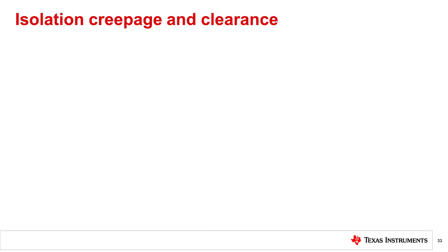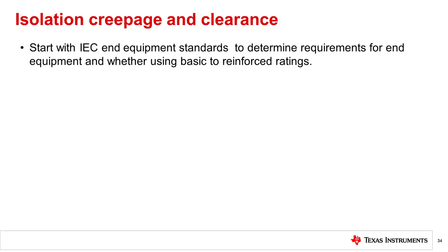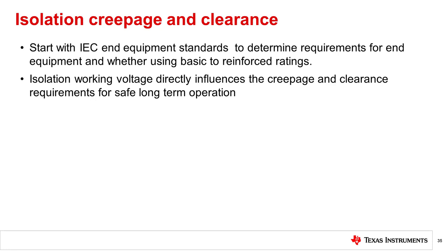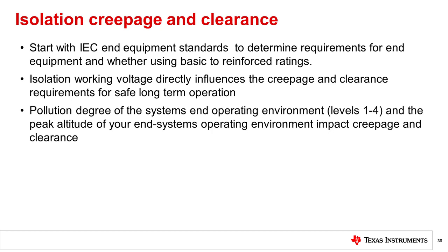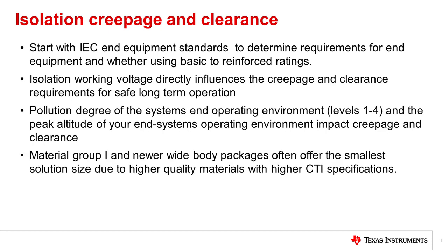This concludes our introduction to isolation creepage and clearance. We outlined a general set of guidelines: understand the required insulation rating of basic or reinforced for your end equipment — the IEC equipment standards are the most common starting point, and creepage requirements may double from basic to reinforced. Identify the insulation working voltage of your system, as this directly influences creepage and clearance requirements. Identify the pollution degree (levels 1 through 4) and peak altitude of your end system's operating environment. Finally, consider the material group category of the isolator — newer wide-body packages often offer the smallest solution size due to higher-quality materials and higher CTI specifications.